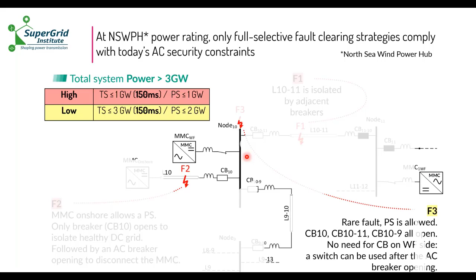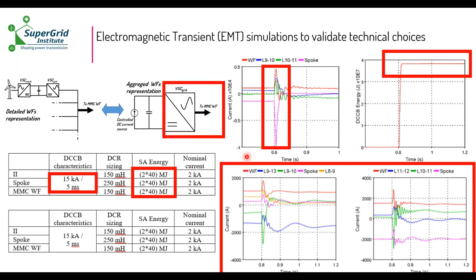I don't have time to go through the simulation, so just to say there are some breaker limits to respect, and some converter limits to respect. So we also performed an EMT during the study to be sure that the choices we made are enough in terms of transient behavior and dynamic behavior of the system. All these limits are checked during this kind of study. So to conclude, of course, we can affirm that the full selective fault clearing strategy is feasible for this kind of network.